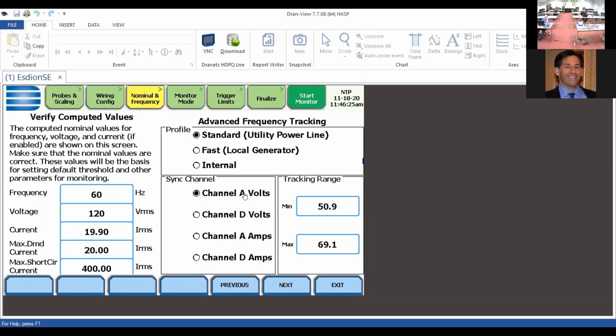The sync channel, like I said, a lot of times is channel A volts. There may be instances related to the type of monitoring application where you'd need to change the sync channel to either channel D volts or even channel A amps. So the instrument has the ability to synchronize from a current signal as well.